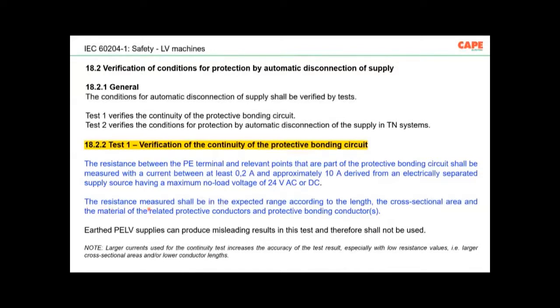Then the resistance measured shall be in the expected range according to its length, the cross-sectional area, and the material of the related protective conductor. So basically, imagine for a typical system, you require 35 square millimeters of copper wire. So after making the connection, you check the resistance of this particular wire, find out the resistance of the wire from the manufacturer's catalog or from the recommendation of the standard, and find out whether the resistance is within the limit. So what do we achieve here? Loose contacts are nullified. You are sure that there is no loose contact. The resistance of the wire is good, so that there is no cut in between.